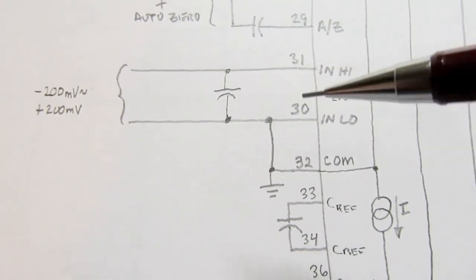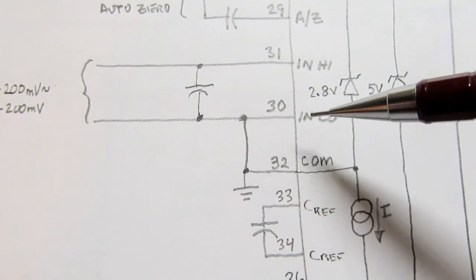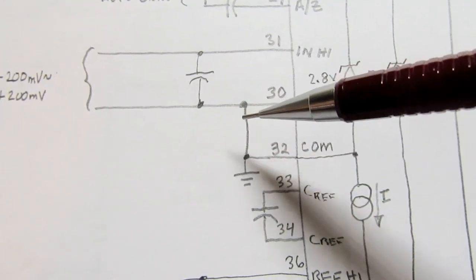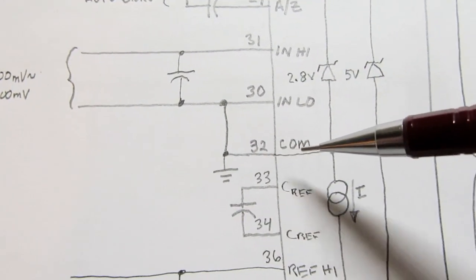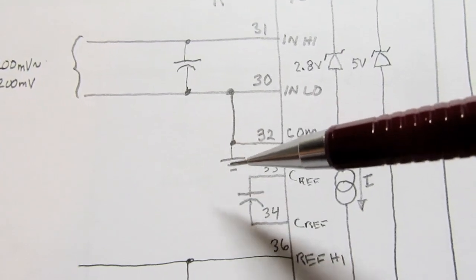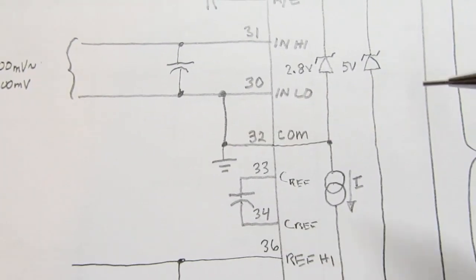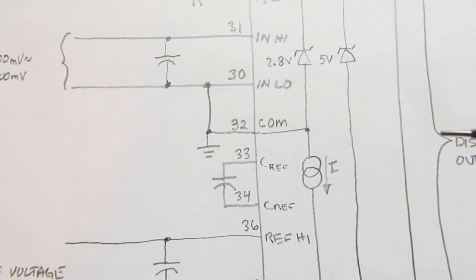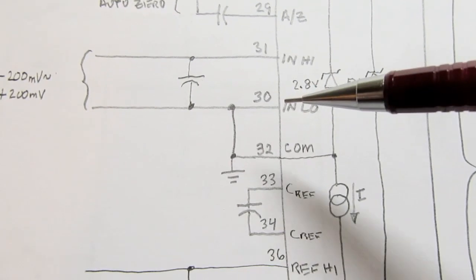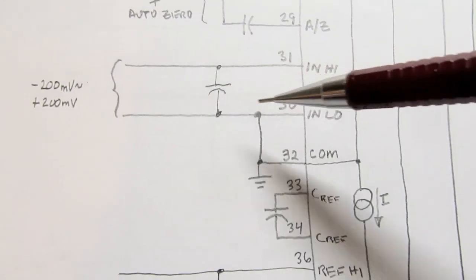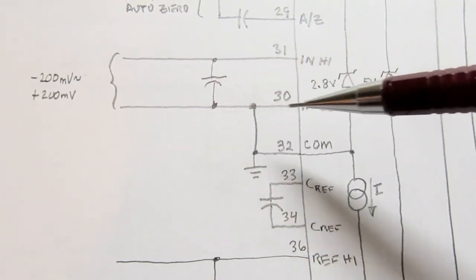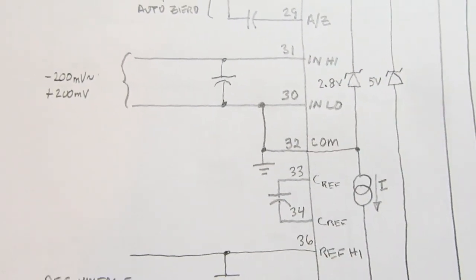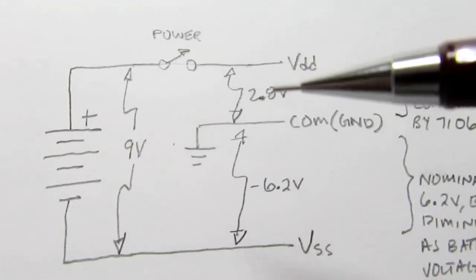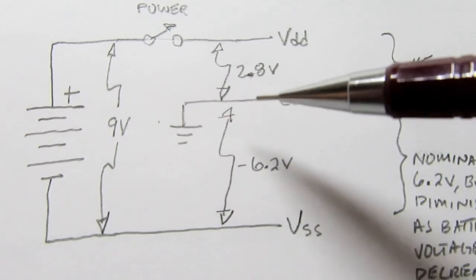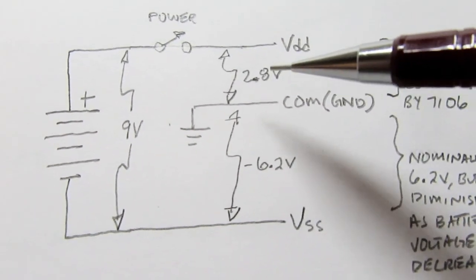Now on this particular meter, the input low signal is always tied to the COM pin and to circuit common or ground. That's not always the case, but on this particular meter that's the way it's done. So the input low is always electrically the same as circuit common. And we know that that means it's always held at 2.8 volts below VDD.